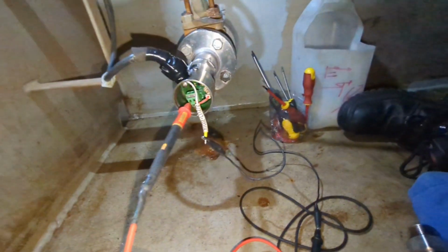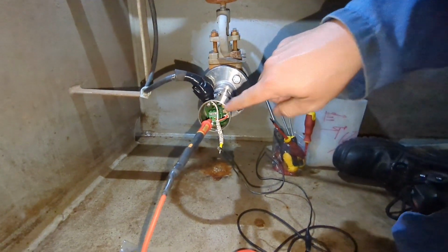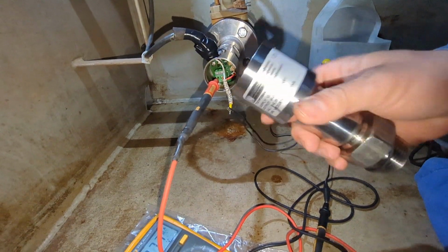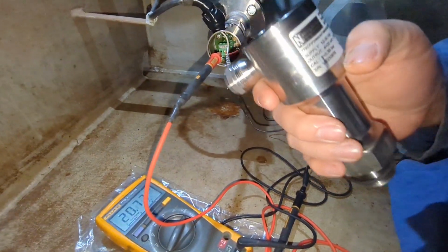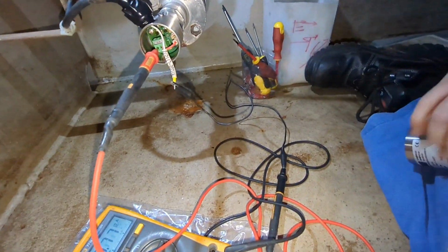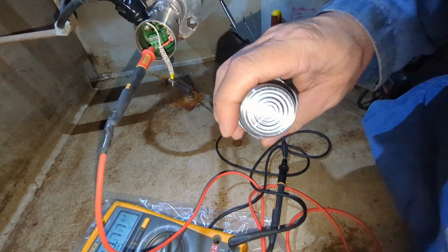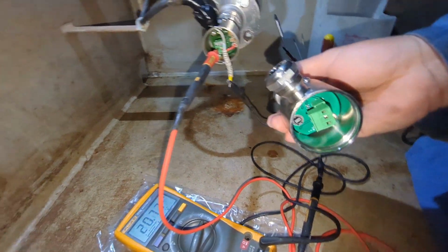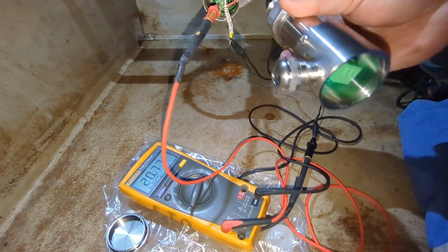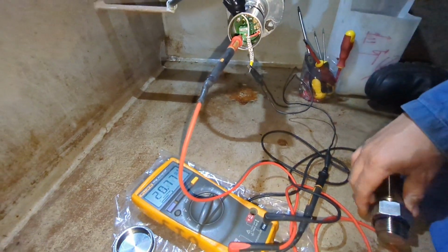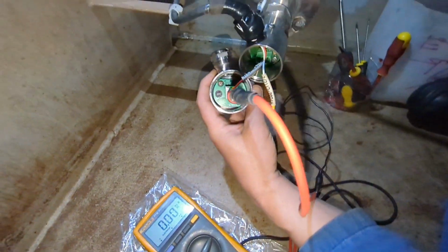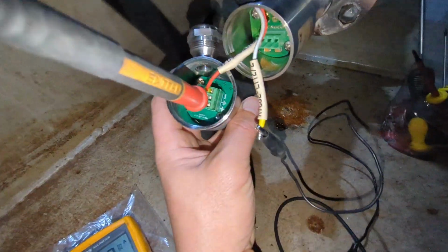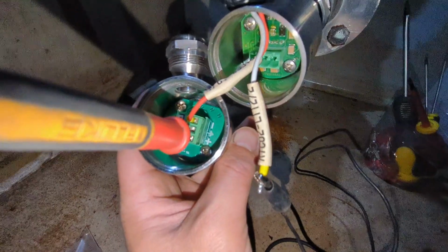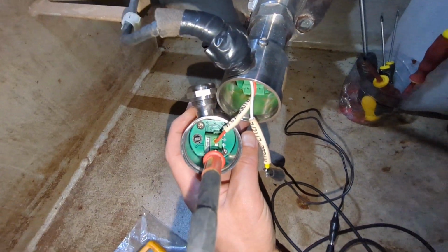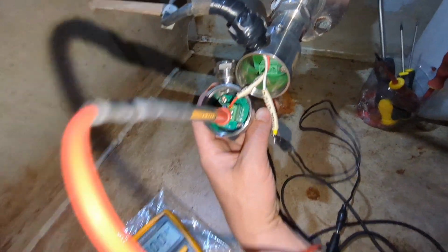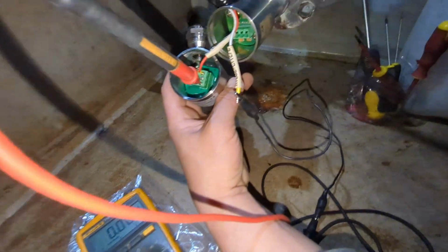So I'm going to simulate and remove this connector. I'm going to put on my new sensor so we can compare how much milliampere value is being generated, provided that this sensitive diaphragm here is free, no pressure at all. So I expected that we are going to measure between 4 milliampere to 6 milliampere. So we can now put it. As you see, since I put a new sensor with the connector, and that sensor having expected 4 to 20 milliampere output, now I have 0 DC milliampere.